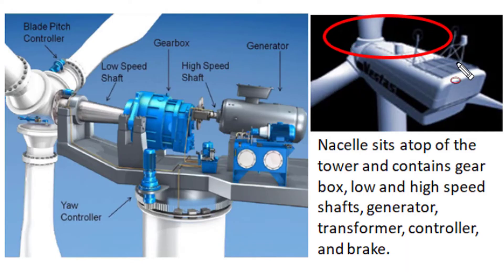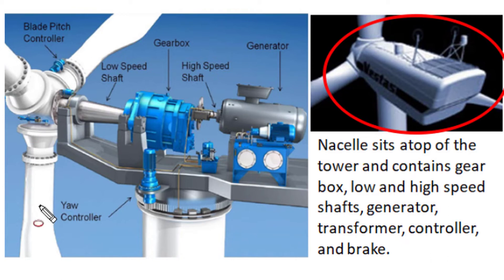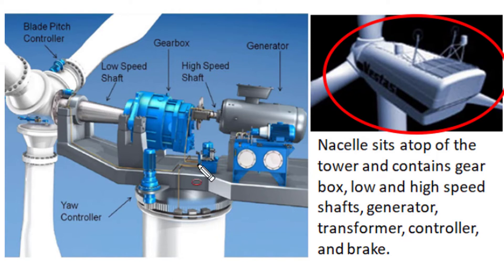The nacelle is the main power center of the wind turbine generator — all energy conversion takes place within this nacelle. It sits on the top of the tall wind turbine tower. On one side of the nacelle, turbine blades are connected to the hub. These turbine blades collect wind energy and convert it into angular rotational motion of high torque and low RPM — typically 10 to 15 revolutions per minute. A gearbox converts this low-RPM, high-torque rotation into a convenient 1000 RPM high-speed rotation for the generator shaft.